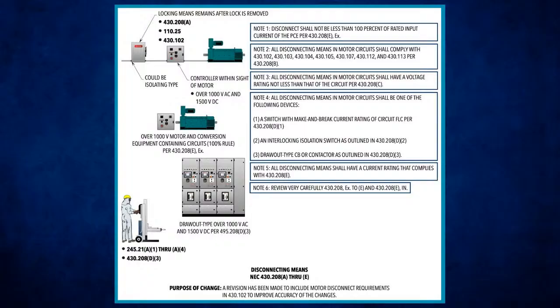When you look at this, they tell you that when you put that disconnecting means in place, you still have to comply with 430.102, and you also have to comply with 110.25 that it has to be lockable. So those are a few things you'll look at.